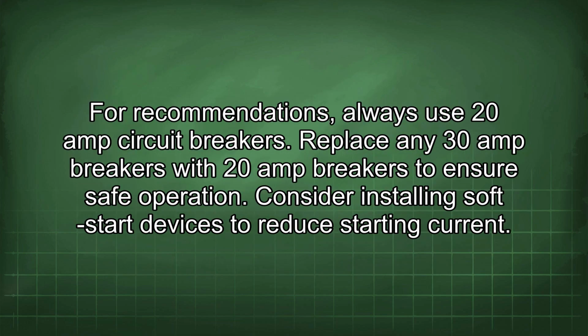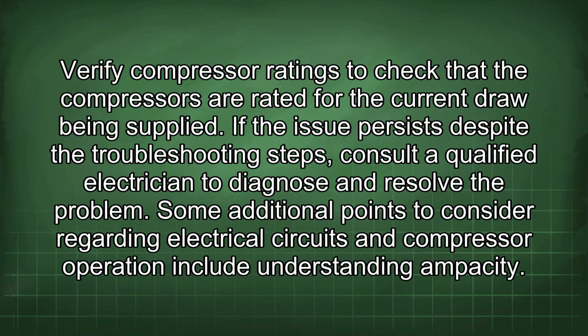For recommendations, always use 20 amp circuit breakers. Replace any 30 amp breakers with 20 amp breakers to ensure safe operation. Consider installing soft start devices to reduce starting current. Verify compressor ratings to check that the compressors are rated for the current draw being supplied. If the issue persists despite the troubleshooting steps, consult a qualified electrician to diagnose and resolve the problem.